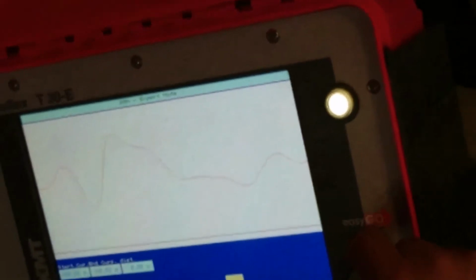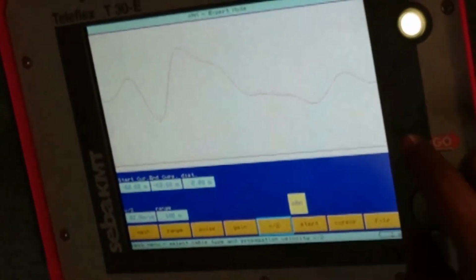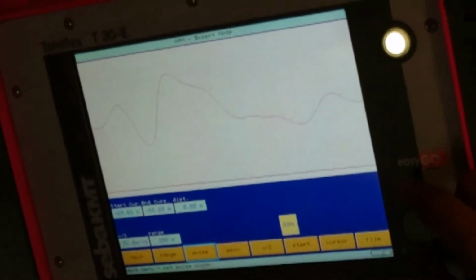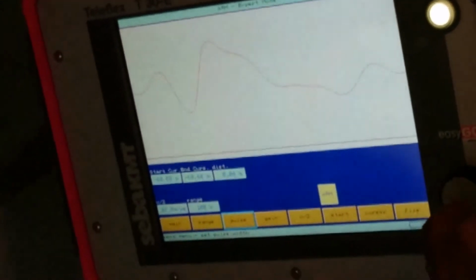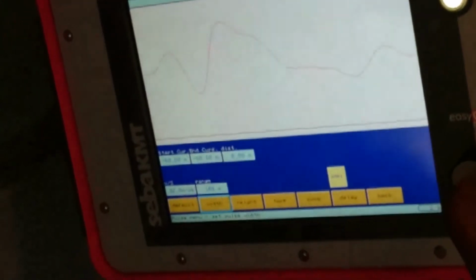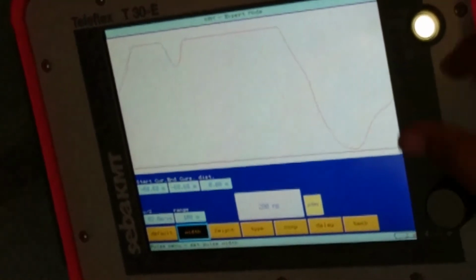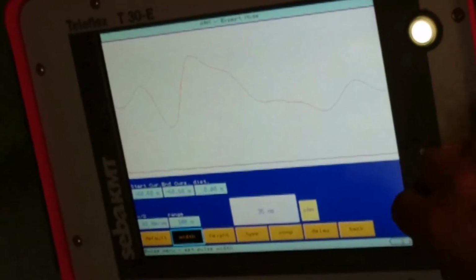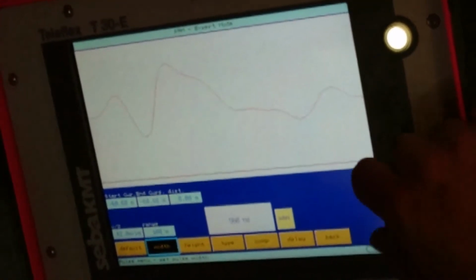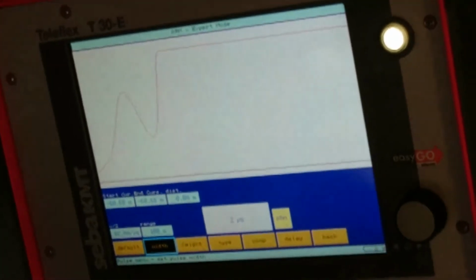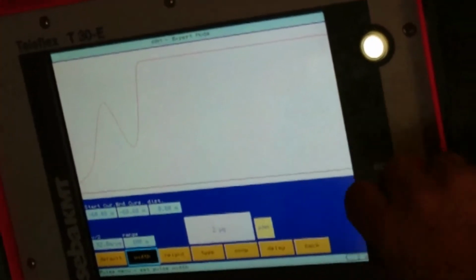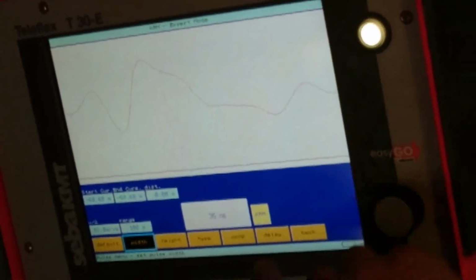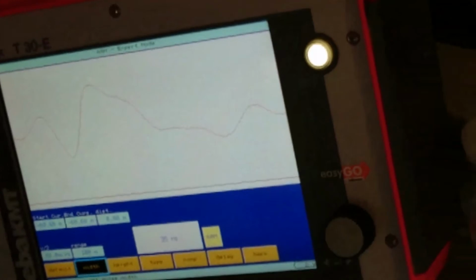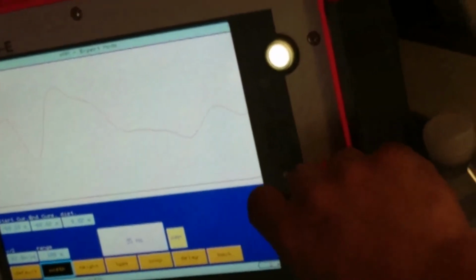Okay, then I go back. Also, I can change the pulse width. If I go very high, then it's not clear, I cannot see where is the end, and if there is a fault I will not see it. 35 nanoseconds is good for a shorter cable. If you have a longer cable, then definitely you should change it to more width.